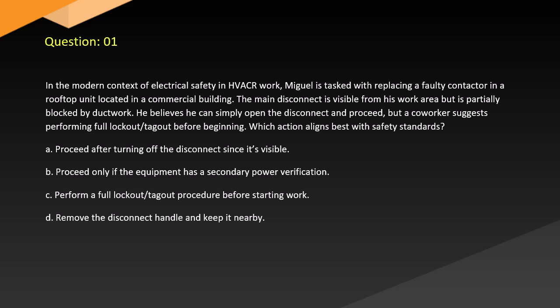A. Proceed after turning off the disconnect since it's visible. B. Proceed only if the equipment has secondary power verification. C. Perform full lockout-tagout procedure before starting work. D. Remove the disconnect handle and keep it nearby.